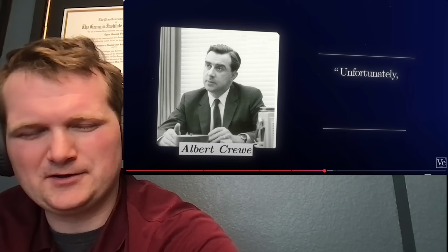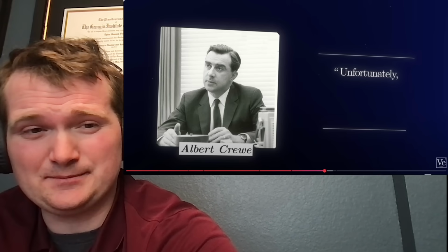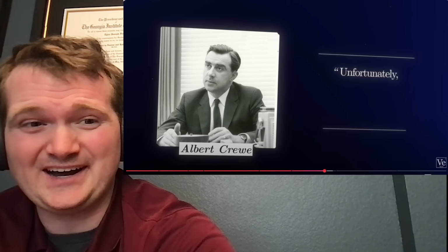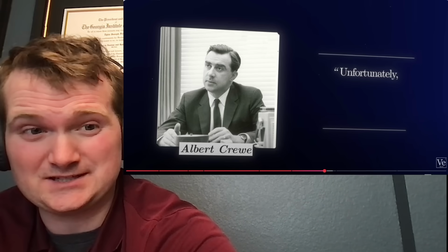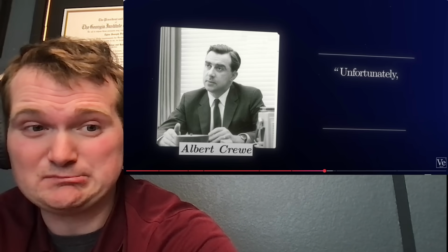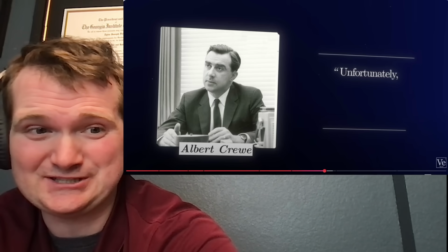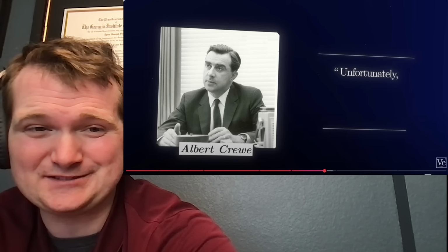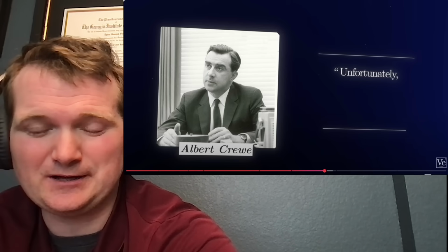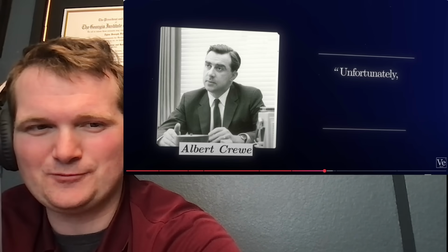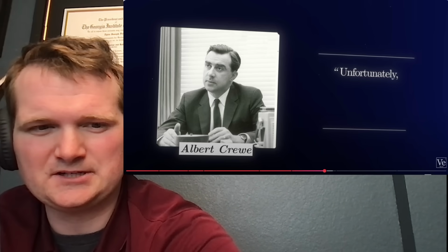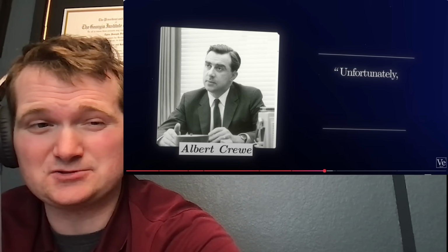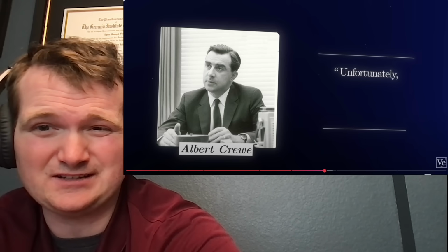One thing about this, the scanning TEM, is it would also involve a higher radiation dose compared to the TEM, because you're simply using more electrons. So you probably couldn't use something like this on a fragile material, but that's a trade-off that you need to make while using this. So it's not completely non-destructive, depending on what you're using this on.